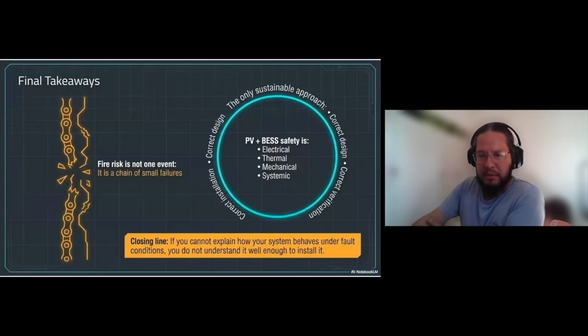If we simplify everything together, PV and battery systems introduce electrical, thermal, and fire risk, all interacting within one installation. Incidents are almost never the result of a single failure, but rather a chain of smaller issues. The goal is not just to install systems, but to understand how they behave, especially under fault conditions. If that behavior isn't properly understood, the system isn't fully under control.